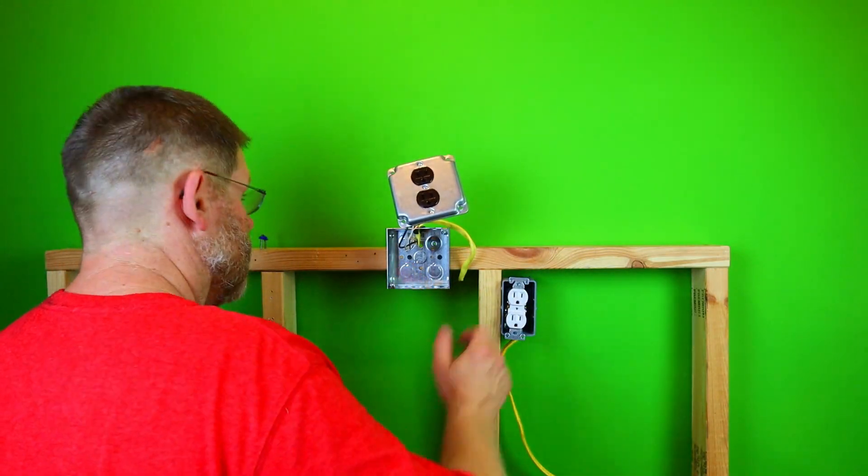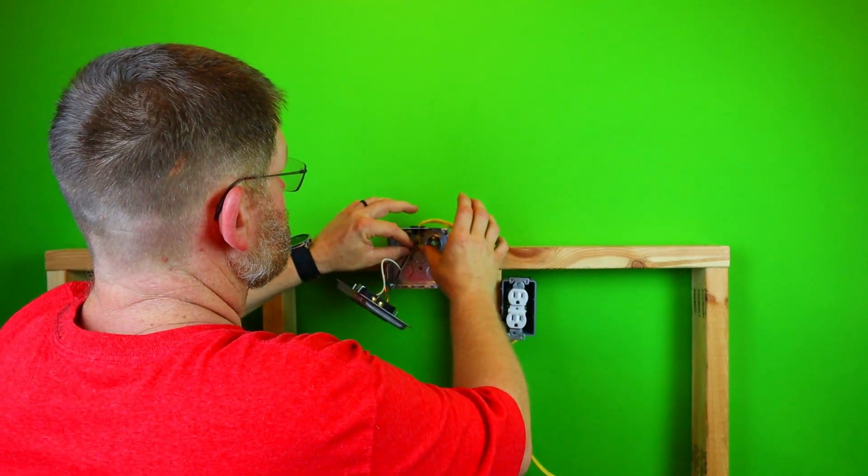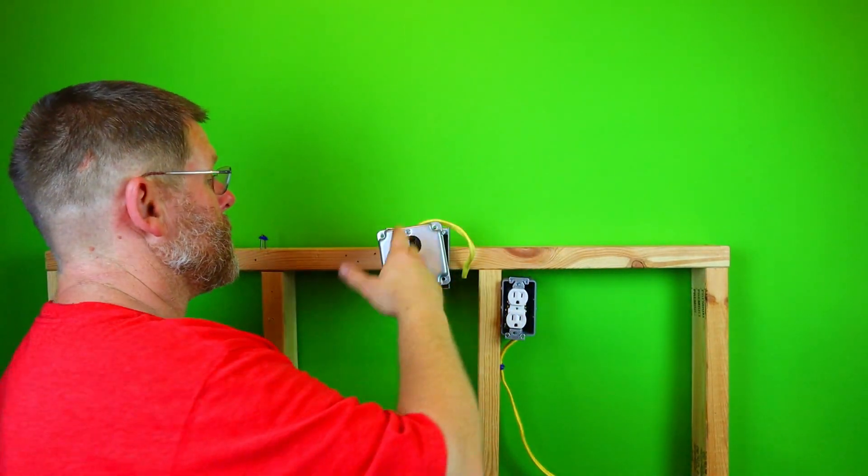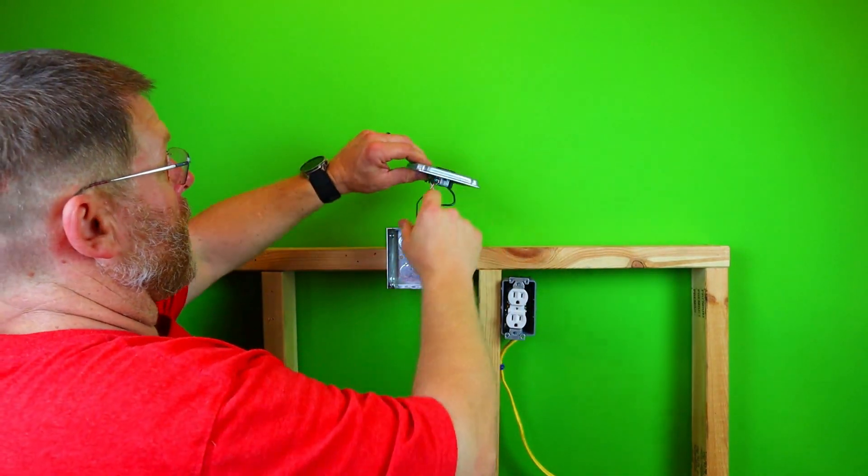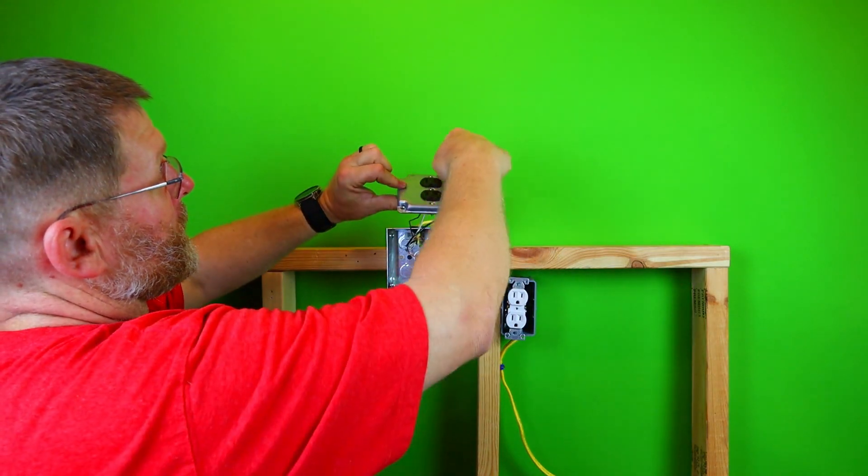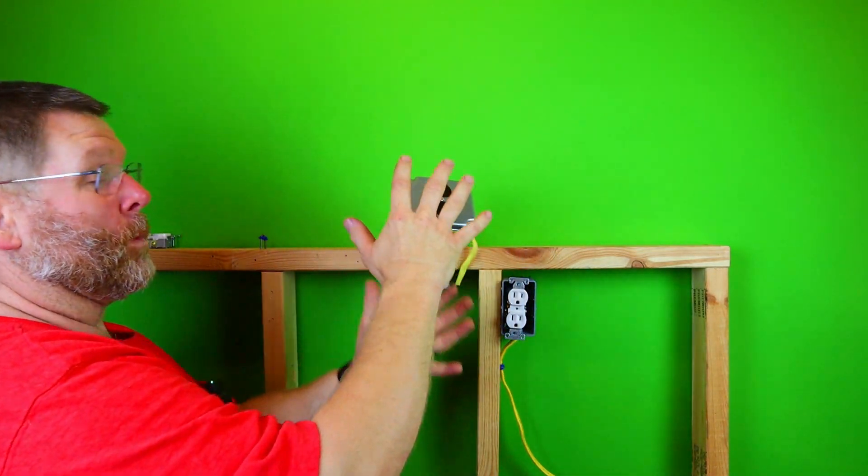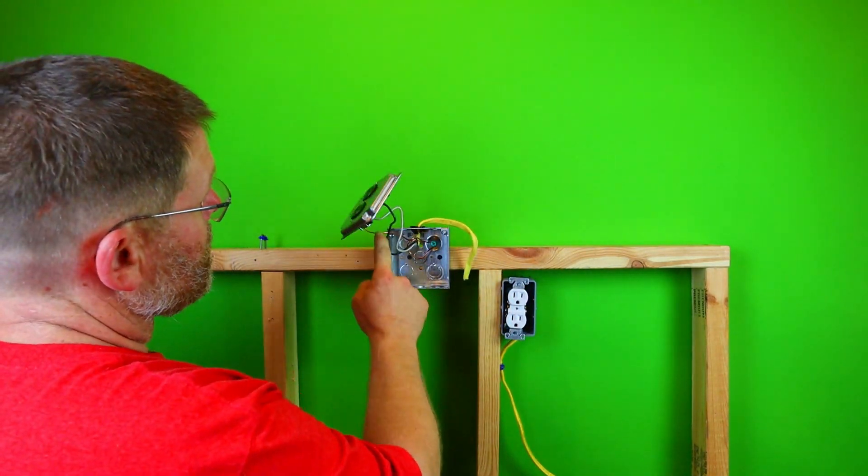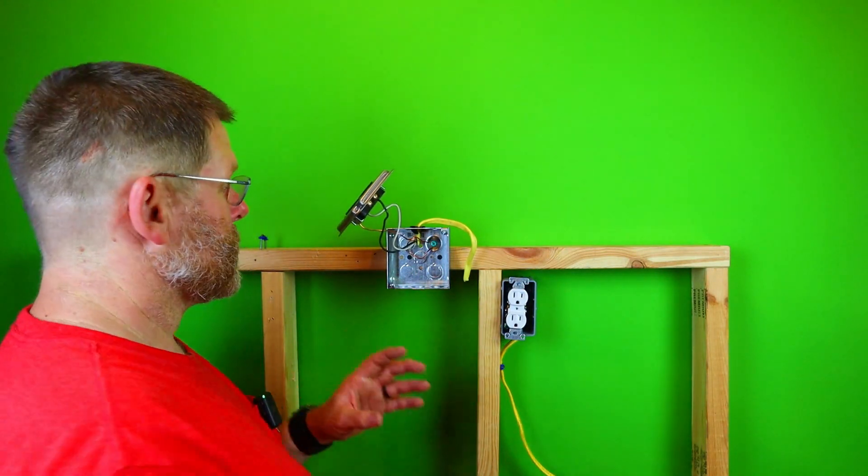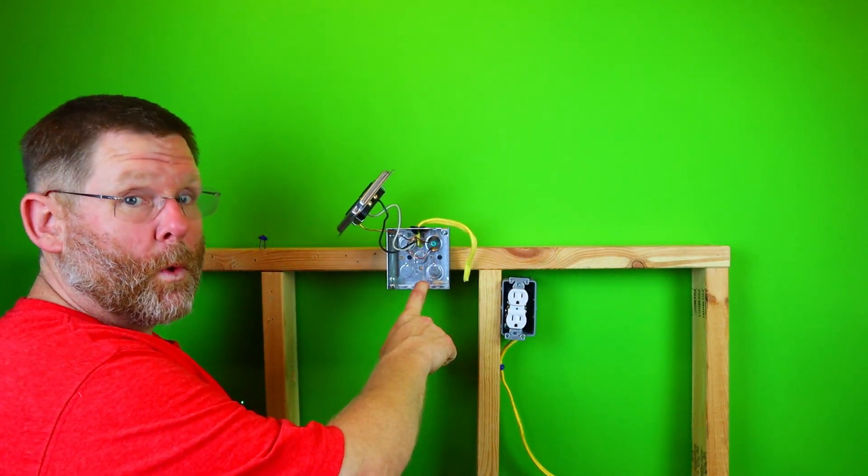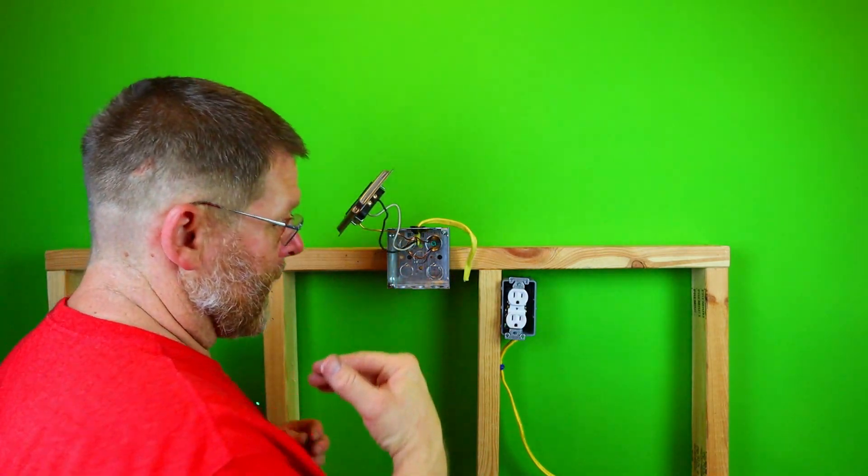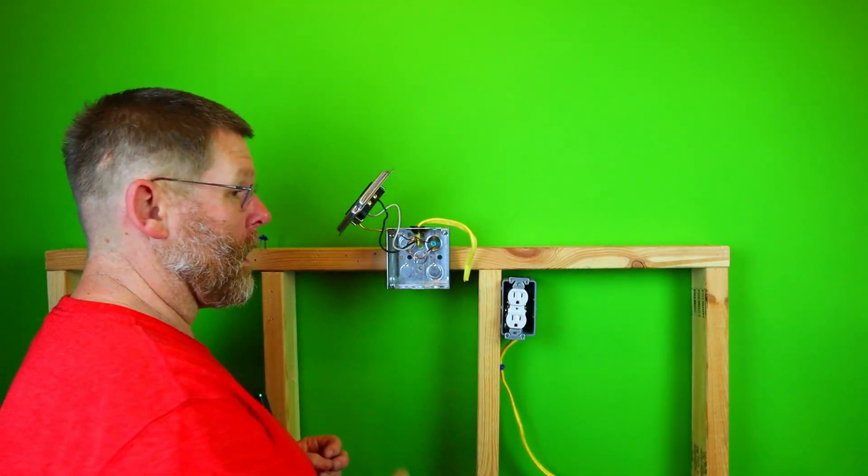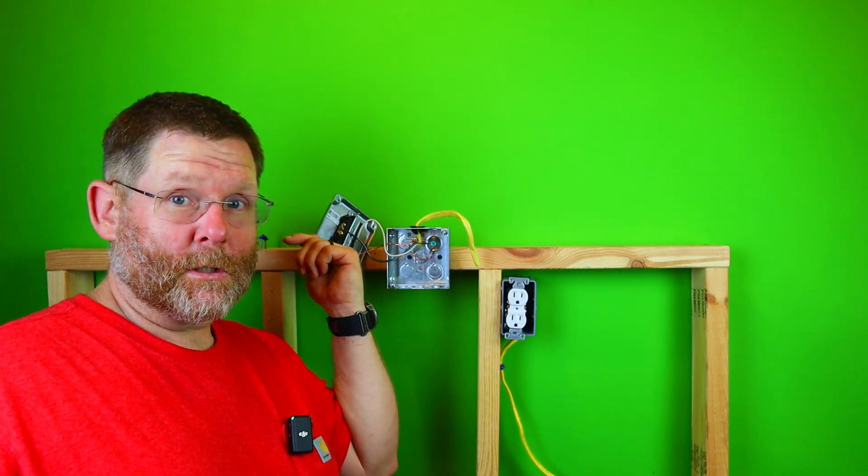And my opinion on this is go ahead and ground the box too. So that way when you pull it out, right, let's look. So we'll ground the box. Let's say you put it back in and everything's working perfect. You have to work on this receptacle for whatever reason. You take this out. All of a sudden, now this ground that was only here and on this plate that was connected to the box is no longer. It's broken. But since you decided to run that ground screw in here, now you have a continuous ground in there. So no matter what happens, if this wire does get loose, it will short out.